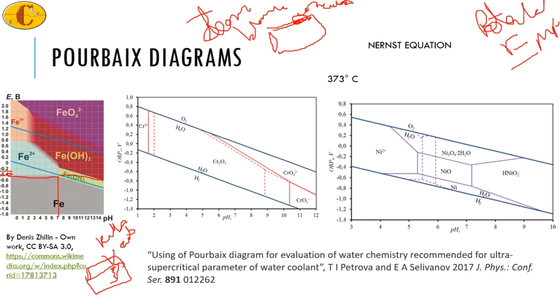If residual stresses from processing or manufacturing are present, or operational stresses such as the high internal pressure in boilers, these stresses add to the pitting and lead to cracking at the base of the pit in carbon steel.